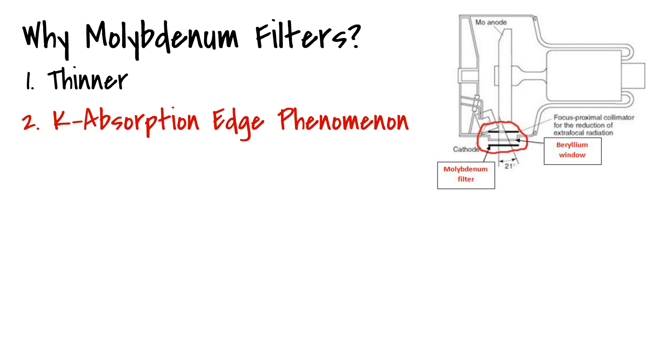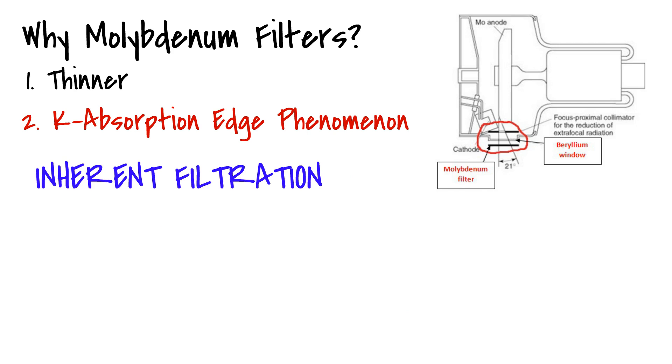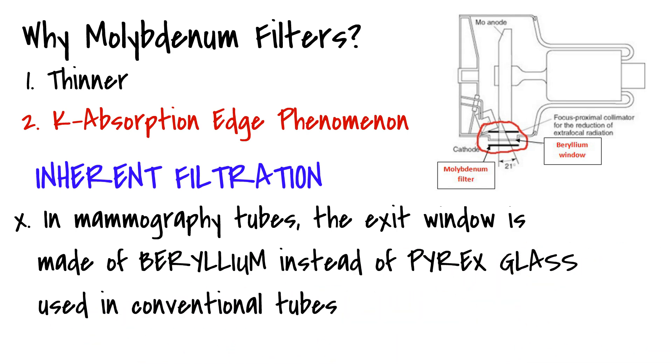So far, we have been discussing added filtration. We should also mention that the mechanism for inherent filtration is also different in mammography tubes. A major source of inherent filtration is in the exit window, which is made of pyrex glass in conventional tubes.